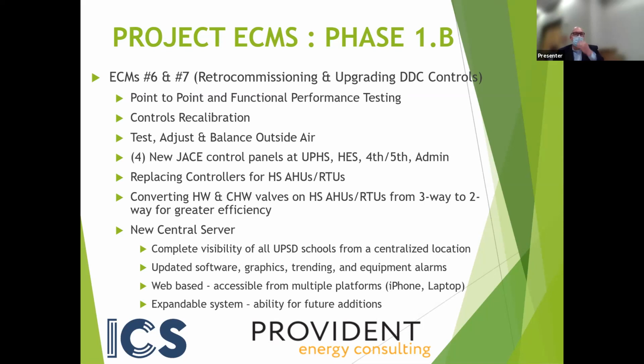So we're going to be putting brand new controllers in there, state of the art. We're also going to be converting a lot of the control valves on these units. The hot water and chilled water systems, the endpoint users, the air handlers, have cooling coils and heating coils on them, and they have control valves on them. The type of technology we're putting in is two-way control valves, which allows us to optimize the pumping systems in the building as well. So it's an energy efficiency measure there too.